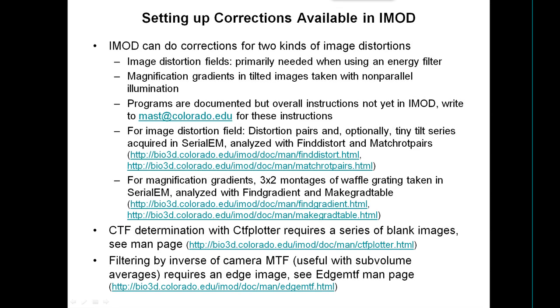For the image distortion field, in SerialEM you take distortion pairs — just four pairs of images — using a routine in the calibration menu, and optionally take little tilt series of about seven pictures. These get analyzed with programs called find_distort and match_rot_pairs. For magnification gradients, it involves taking 3x2 montages using the waffle grating at high tilt, and those get analyzed with find_gradient, then a table is made with make_grad_table.